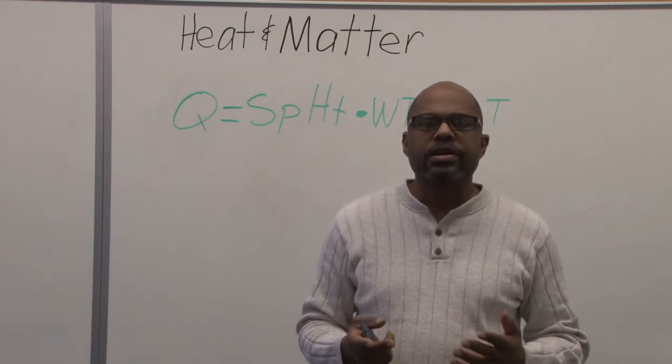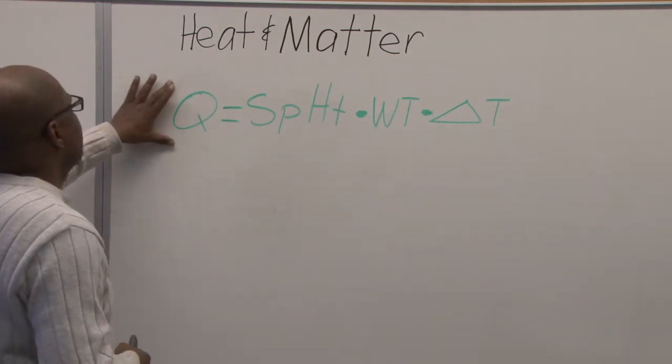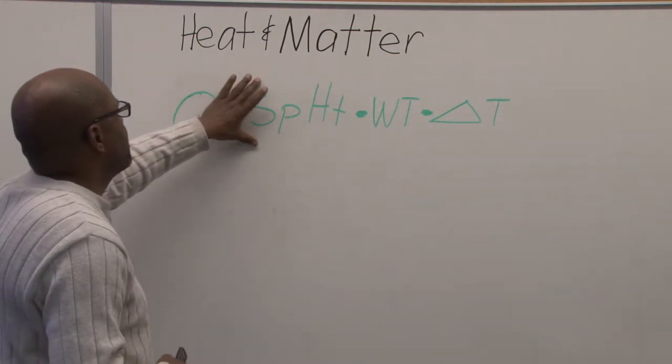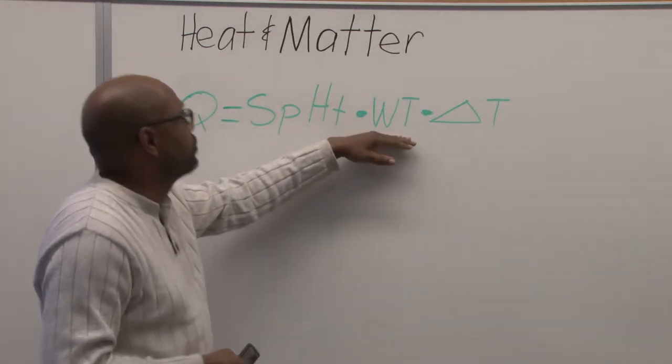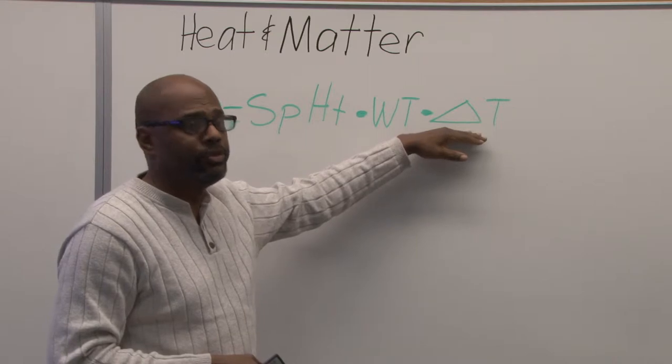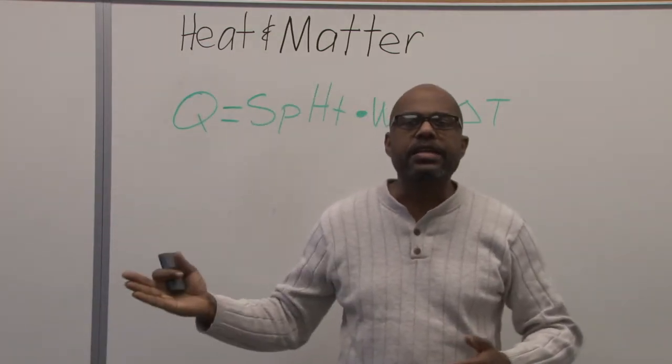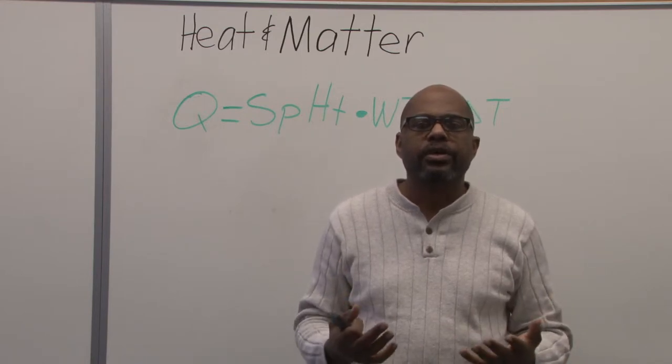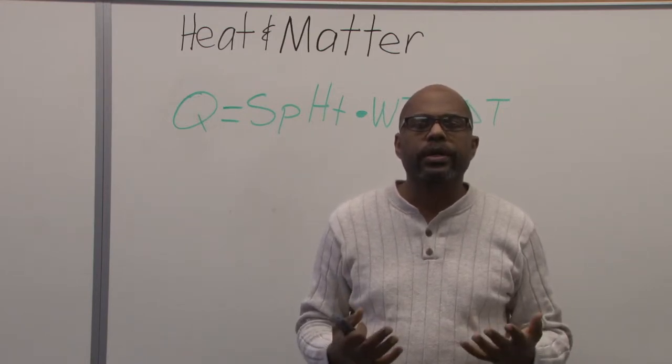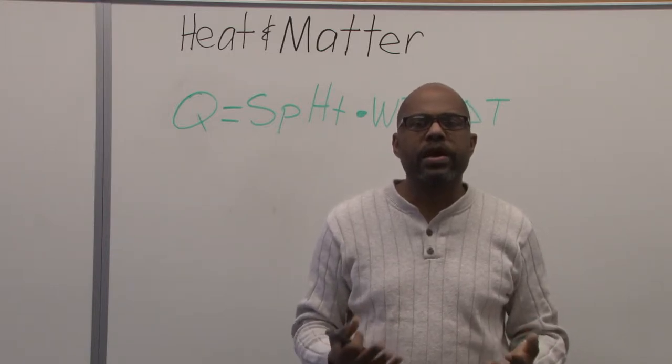As we look at heat and energy, we can quantify it by looking at the quantity of energy equals the specific heat times the weight of that substance times the change in temperature. So the definition of a specific heat is the amount of energy it takes to raise or lower one pound of a substance one degree Fahrenheit.